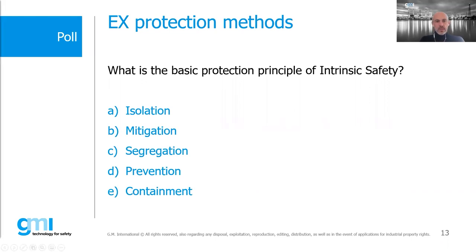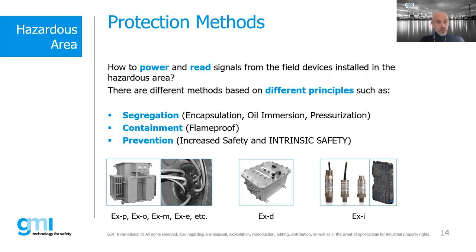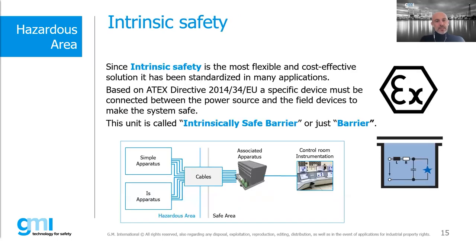Regarding protection methods: how do you power and read signals from field devices installed in hazardous areas? There are different technologies. Segregation involves hardware that is encapsulated, immersed in oil, or pressurized in cabinets. Containment involves flameproof boxes — large aluminum enclosures. Then there is the protection method of increased safety and intrinsic safety. Intrinsic safety has less impact on systems because it prevents energy at the source — it is very flexible and cost-effective compared to other technologies.